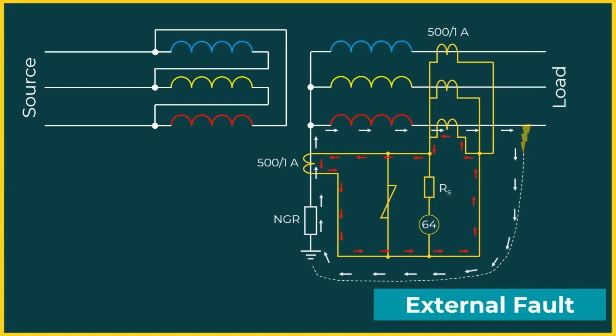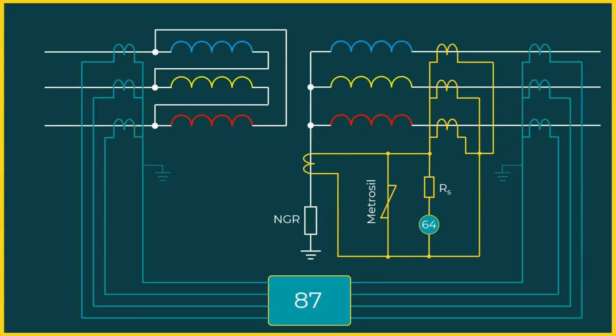The key takeaway is this: differential protection is excellent, but it is not enough on its own. It cannot detect all earth faults, especially those on the LV winding of the transformer. REF fills this gap, ensuring that the entire winding is covered. For critical and expensive assets like power transformers, relying on the differential relay only is risky. Combining it with REF protection ensures complete, fast, and sensitive fault detection. In short, if we want dependable transformer protection, REF is not optional, it is necessary protection.